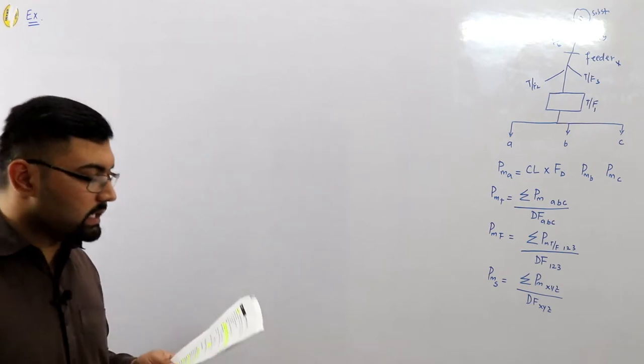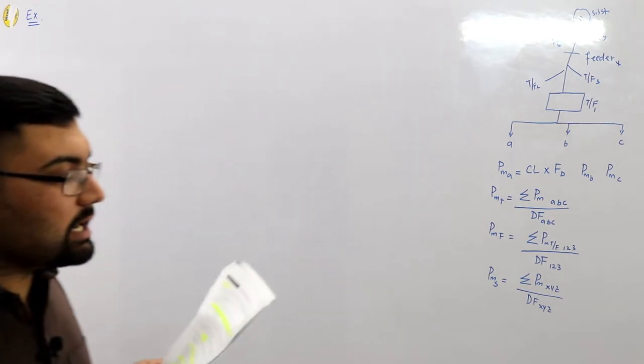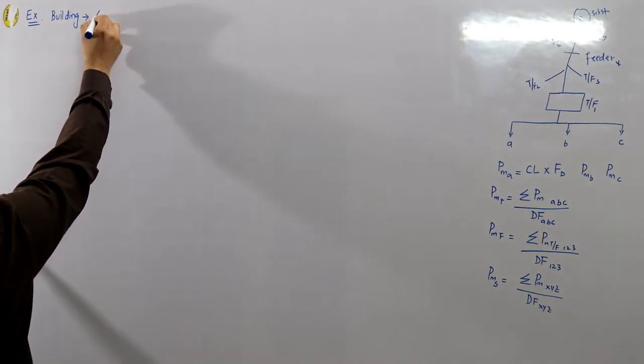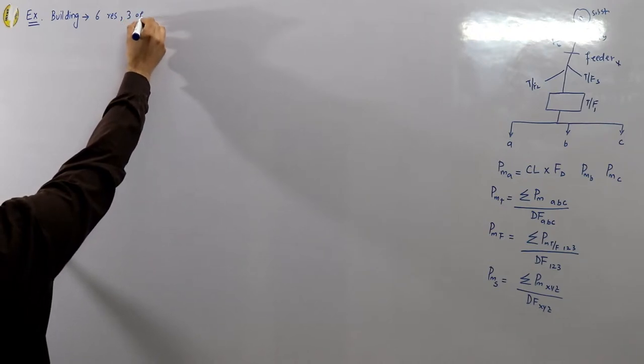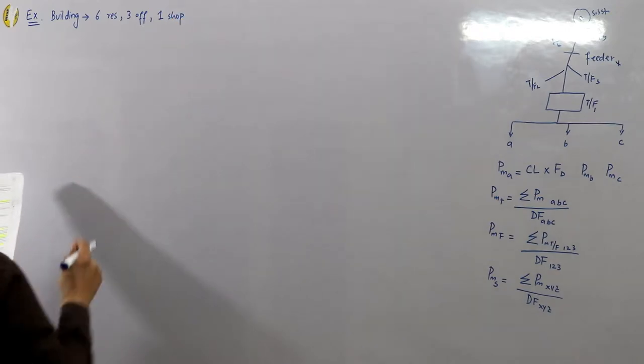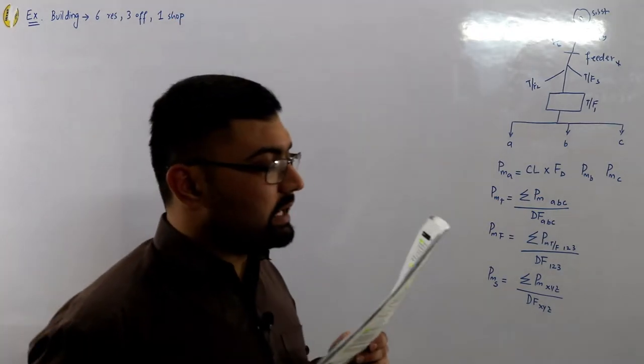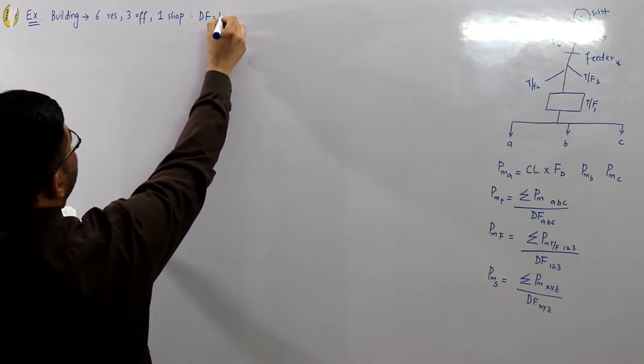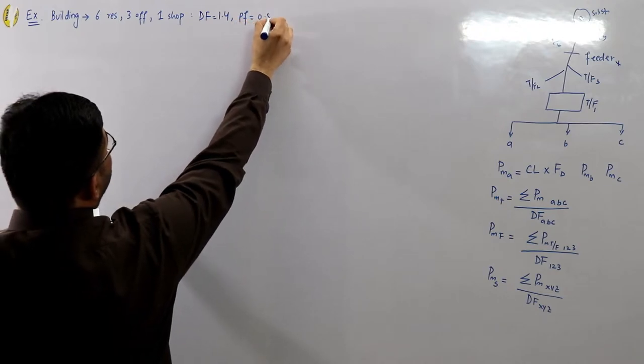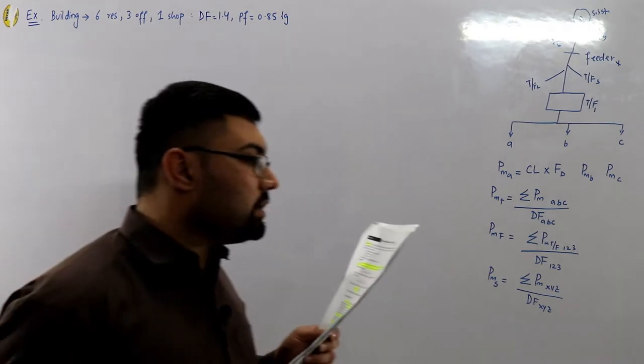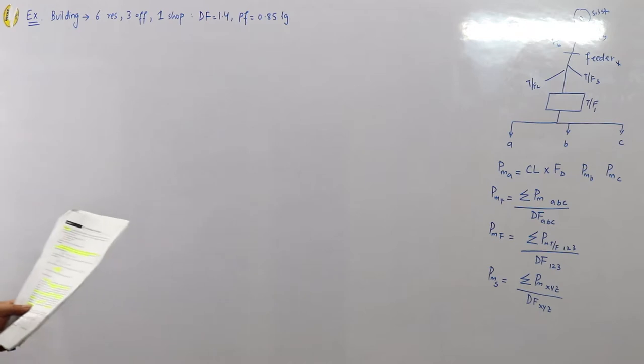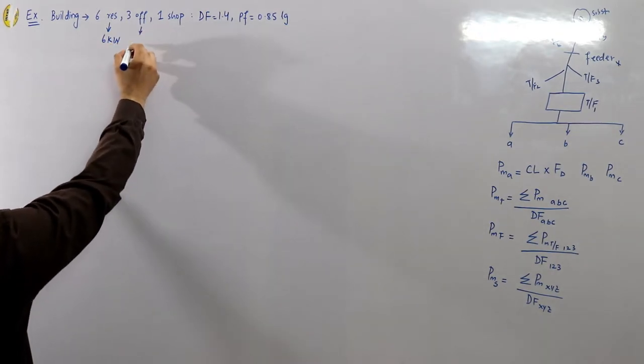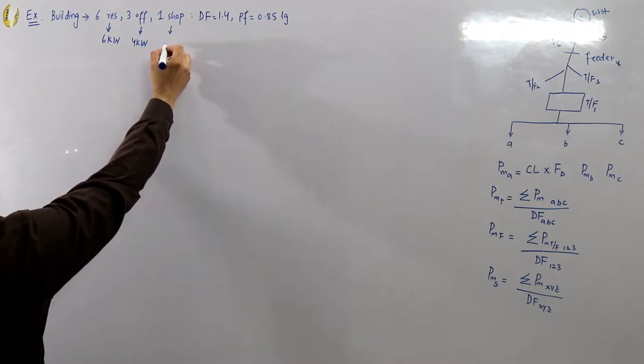The first example: a metropolitan building with six residential apartments, three offices, and one shop. This building has an overall diversity factor of 1.4 and a power factor of 0.85 lagging. The connected load of each entity is given — each residential apartment has a load of six kilowatts, each office has four kilowatts, and the shop has 3.5 kilowatts.